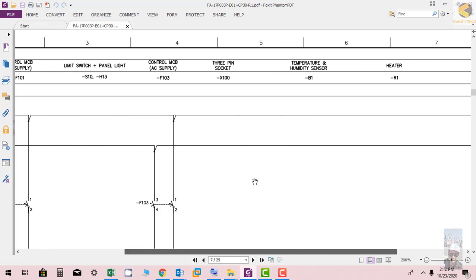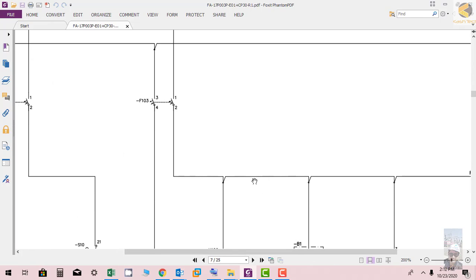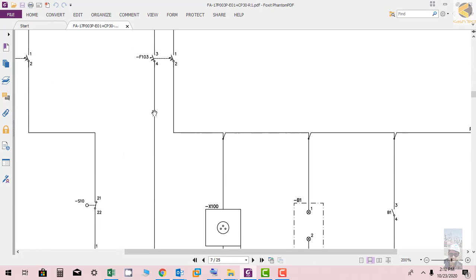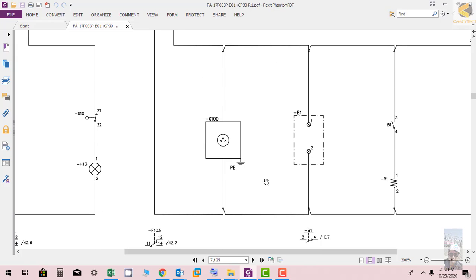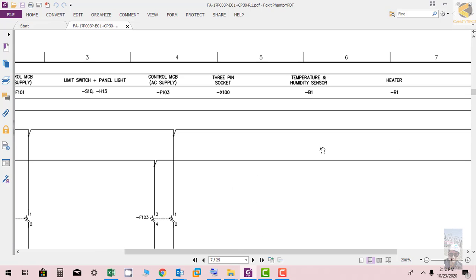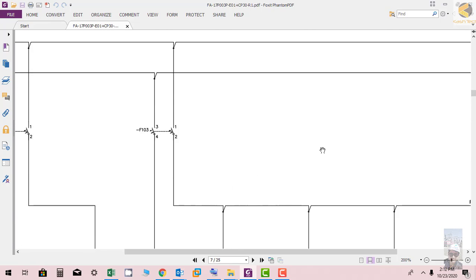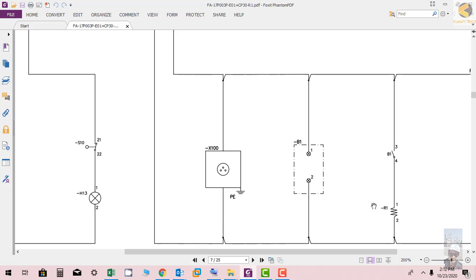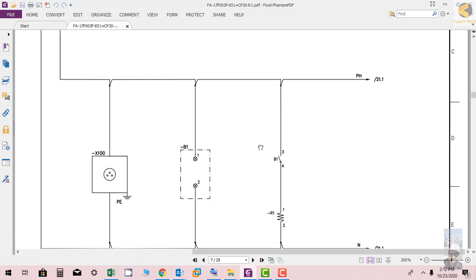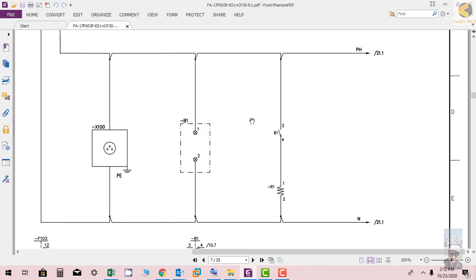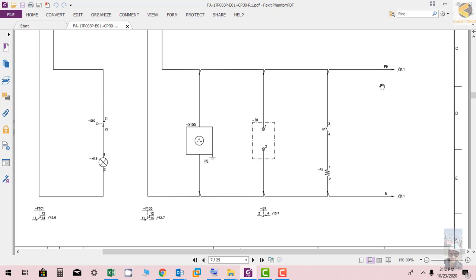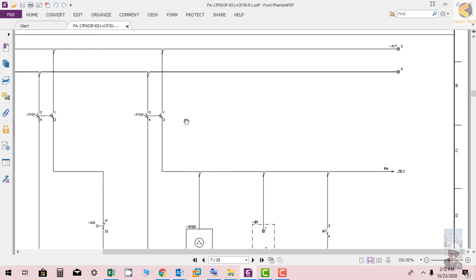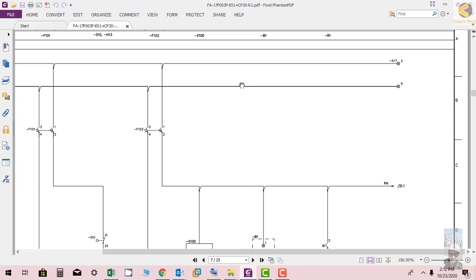The second supply is going through F103 MCB. It is empowering the AC socket. This is the thermostat which is monitoring the humidity and the temperature. Then it has a space heater, so if the values are below the settings, the humidity is high or the temperature is low, then this given contact will close, it will energize the space heater. When it's working it will reduce the humidity and increase the temperature. It is used to remove the rust.